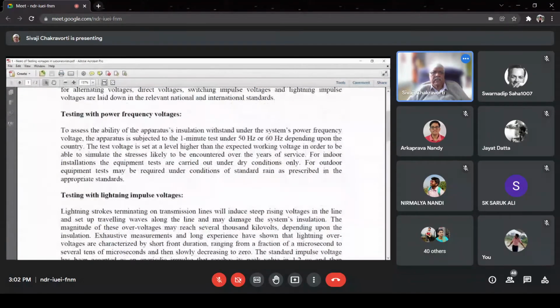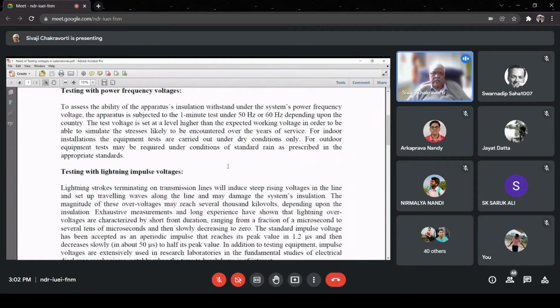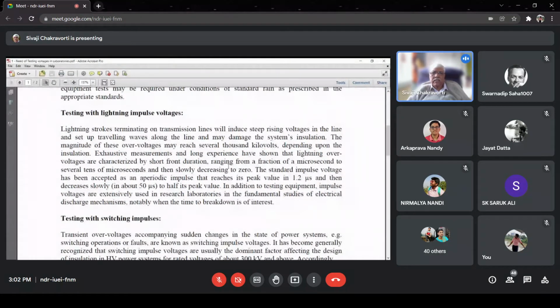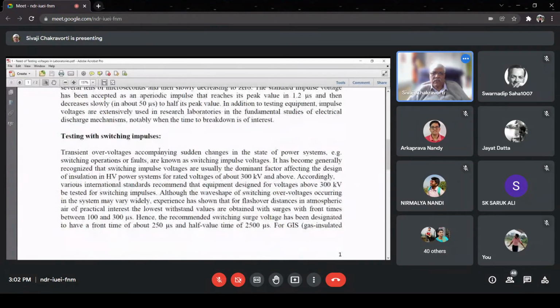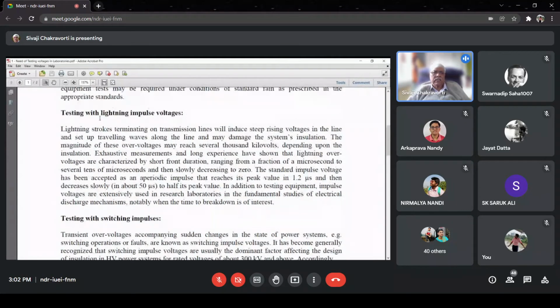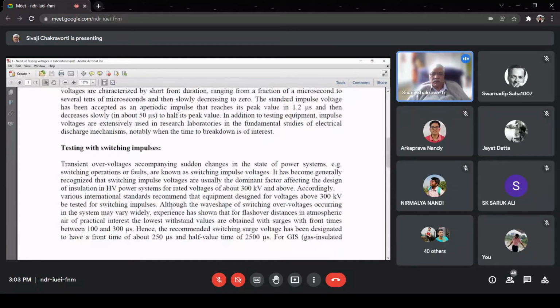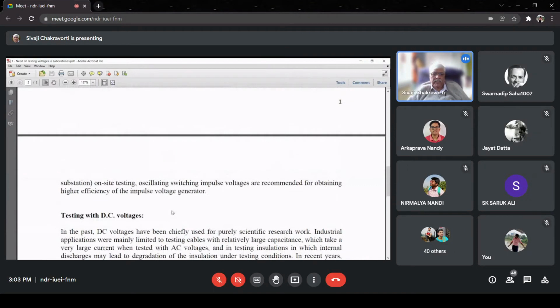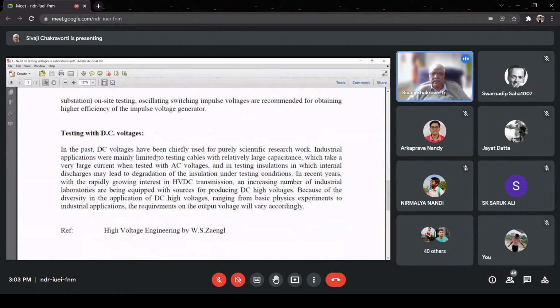Once again, I repeat, one is testing with power frequency voltages, that means AC 50 Hertz. Testing with lightning impulse voltages, that means the voltage waveforms which is similar to the waveforms that we get in natural lightning. Then testing with switching impulses, that means the waveforms that we get when the components are being switched in our power system. By the way, there is another way we define it, that lightning impulse voltages are also called the external over voltages because they are not generated within the system, and the switching impulses are called internal over voltages because they are generated within the power system. So that is also another way of representing these over voltages. And then finally the testing with DC voltages.